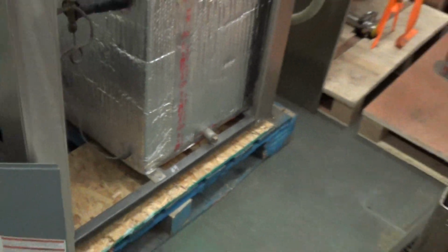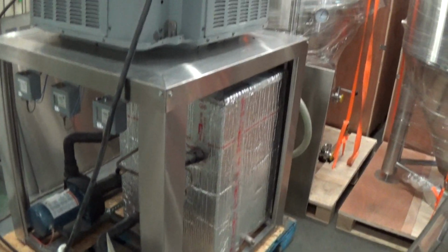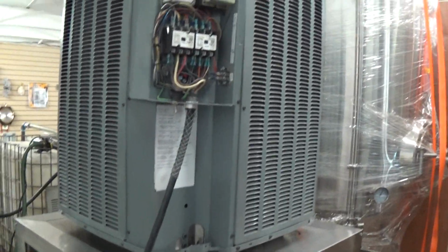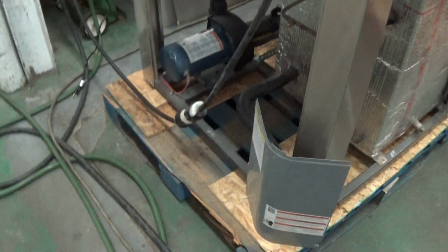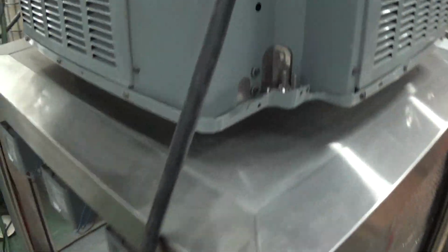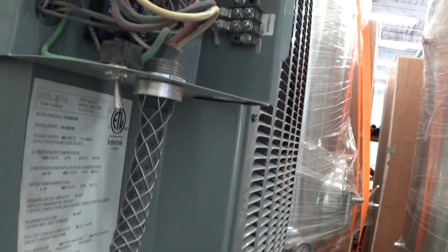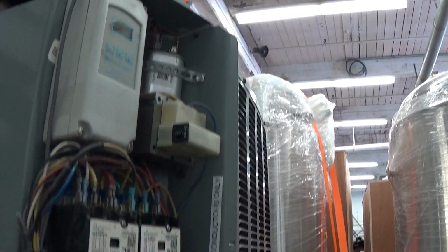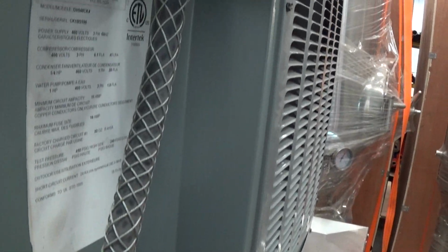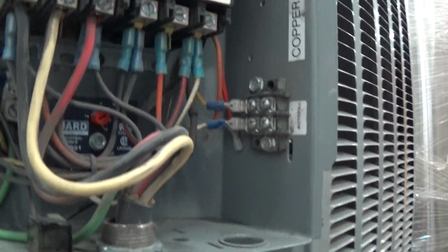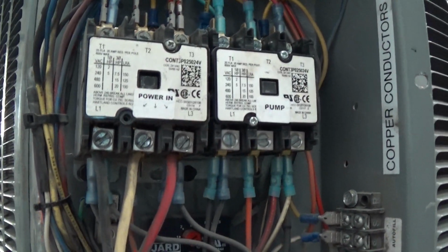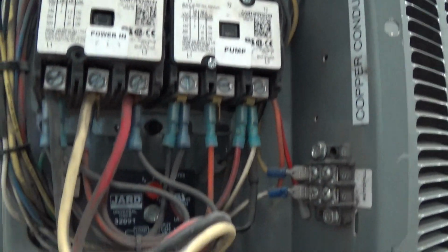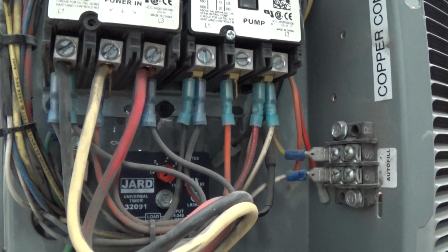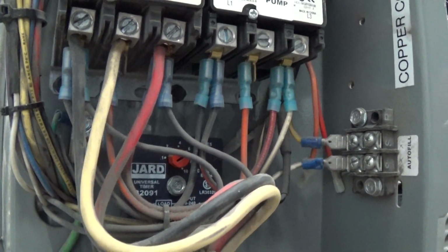We have all the stainless side covers off the unit right now, just for the runoff. When you first bring power to it, you or your electrician will bring power up to the bottom of this little electrical enclosure, and again we have the cover off of it, and that's where the controller is. You're going to bring power into here, to the left contactor where it says power in, and you'll see we have 3 hots, black, white, red, and a ground.